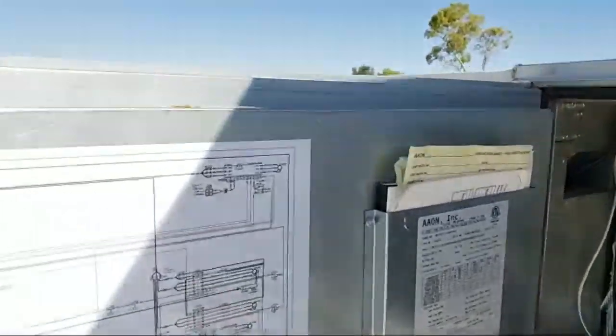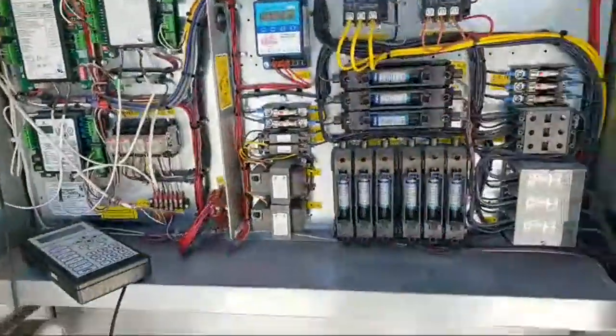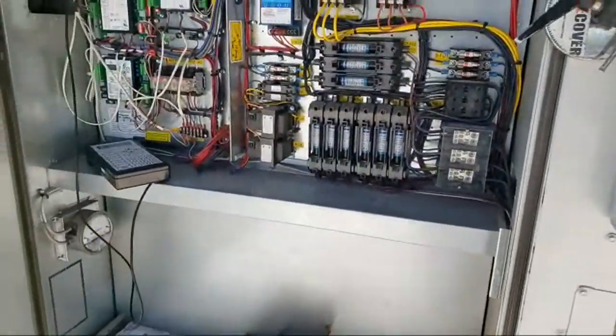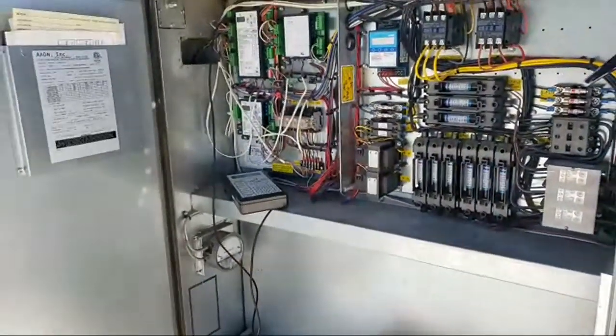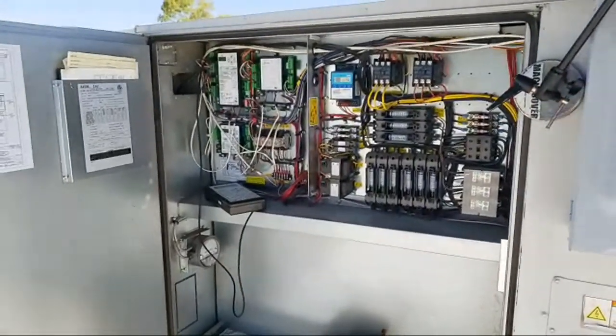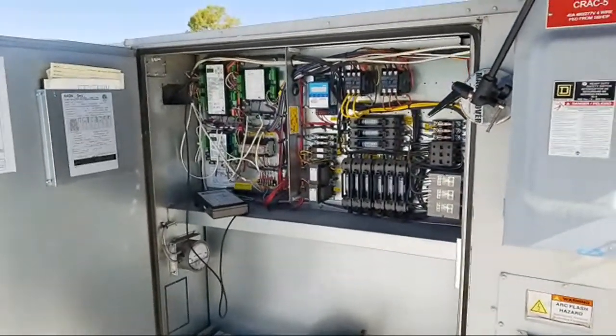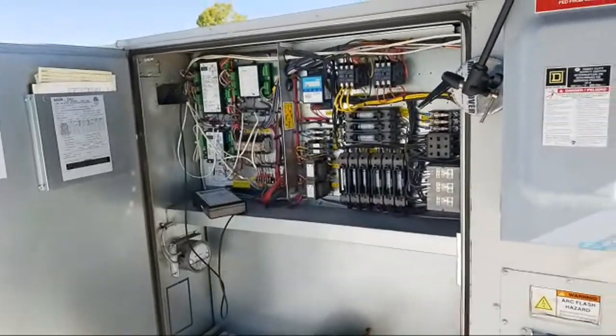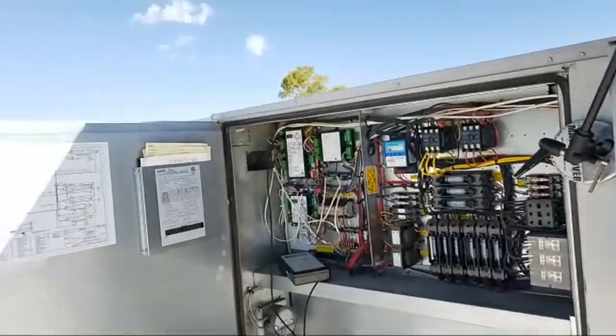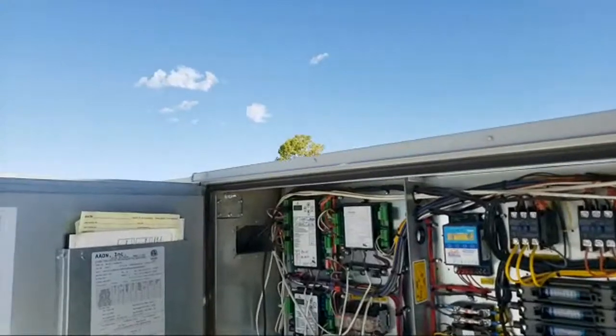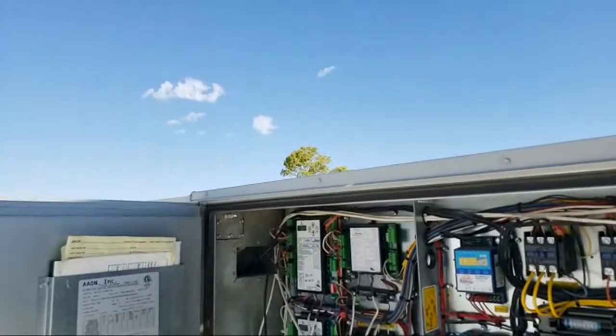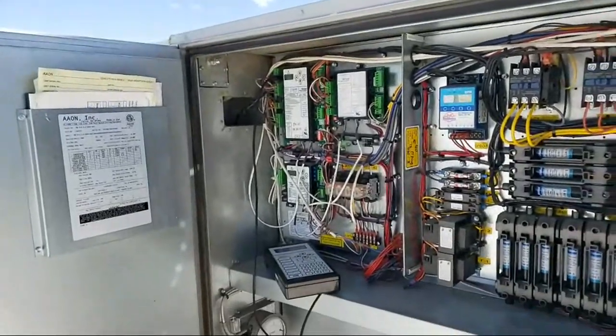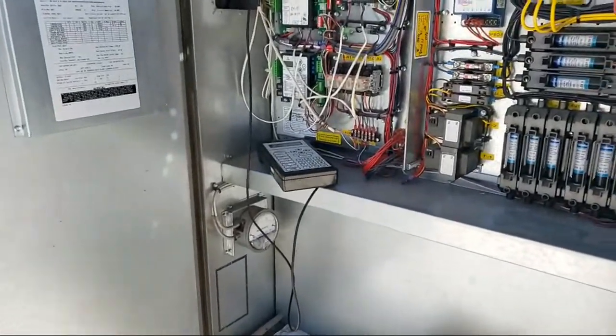A few of these units are cooling the server room, and he's been complaining that it's way overcooled. I guess it's been getting down to like 58 degrees and sometimes down to 55 or even colder in there. Meanwhile, it's 105 to 110 outside. But we've been experiencing monsoon weather where the humidity's been up there a little bit. Right now, the humidity is at a nice low 32% with about 90 degrees outside. Might be more like 92, 93 by now since the last time I looked.